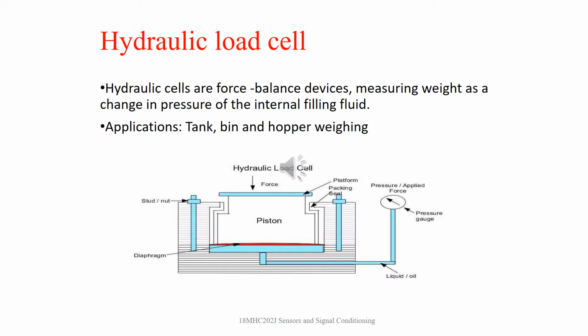So we have types in this, such as the rolling diaphragm type. A load or force acting on the head is transferred to a piston that in turn compresses a filling fluid. As the force increases, the pressure of the hydraulic fluid increases. This pressure can be locally transmitted for remote control. Here, the output is linear and relatively unaffected by the amount of filling fluid. If these load cells are properly installed and calibrated, accuracy will be better. Typical hydraulic load cell applications include tank, bin, and hopper weighing.